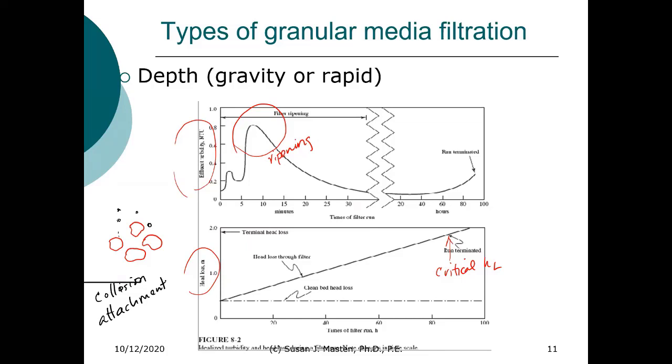What happens is that as one particle collects, we have multiple particles. It's more likely that the next particle will attach to the removed particle than it will the media itself. So you actually get, in this initial period of time, an improved removal.